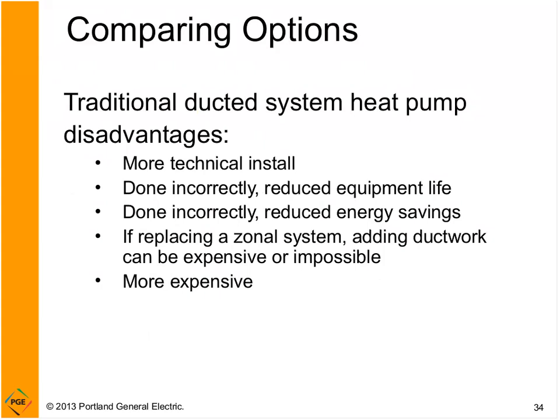Comparing options. So traditional ducted system heat pump disadvantages. A ducted system is a more technical install. The installation requires proper airflow, which means duct sizing requirements and other considerations. So if done incorrectly, there's reduced equipment life. So if there's not enough airflow, it could harm the compressor, for example. And if done incorrectly, there's reduced savings.